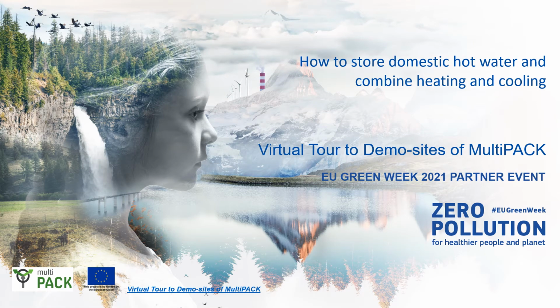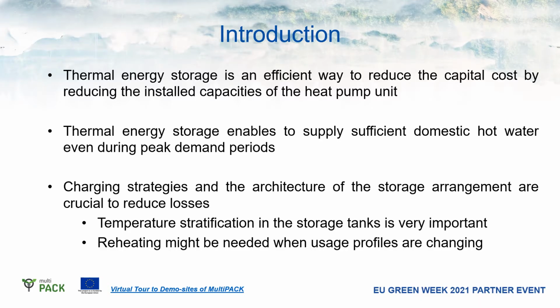Welcome to a presentation on how to store domestic hot water and combine the heating and cooling in newly developed MultiPACK heat pump chillers. The important thing with heat pumps is also that there is thermal storage, because then we can reduce the capital cost, because the installed capacities of the heat pump can be utilized to charge the storage device. Then this thermal energy storage device enables us to supply sufficient domestic hot water even during peak demand periods, which have been accumulated during the rest of the period.